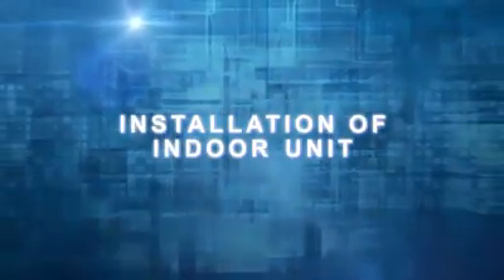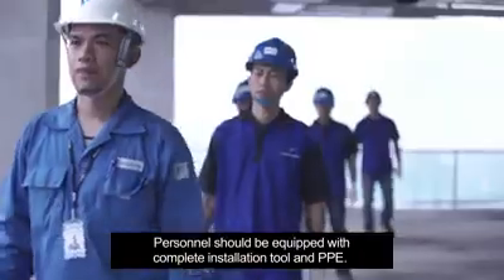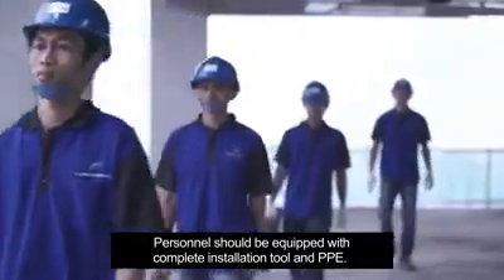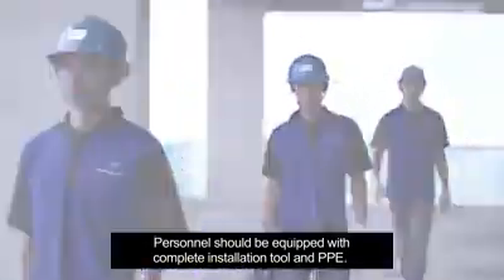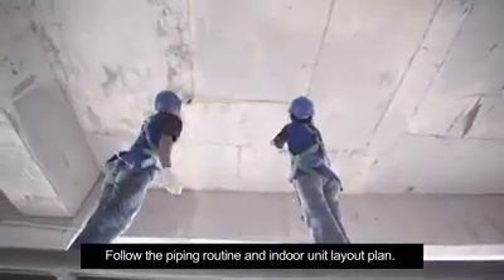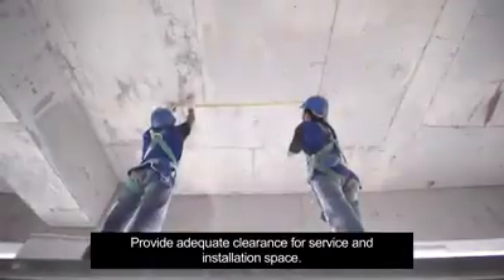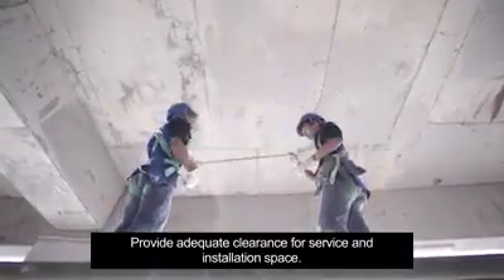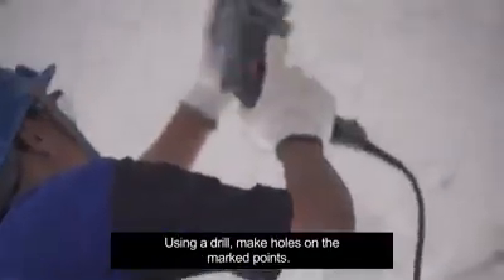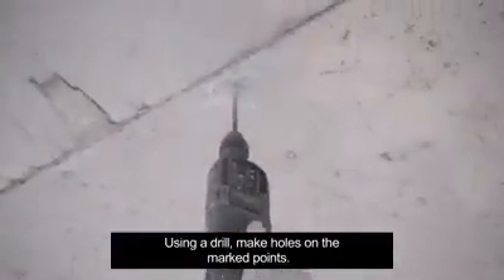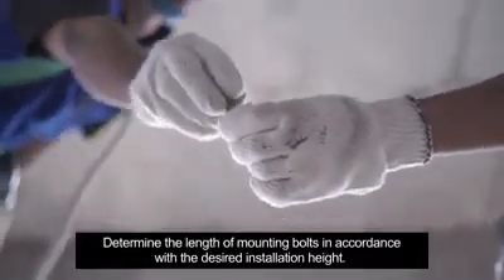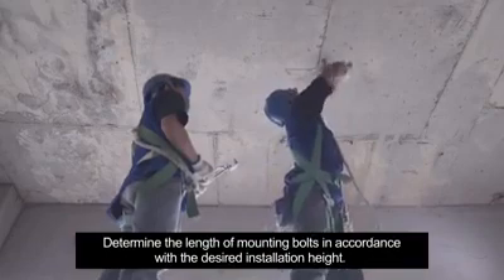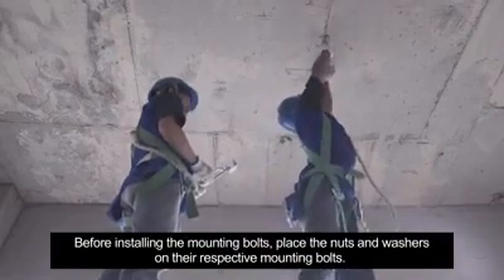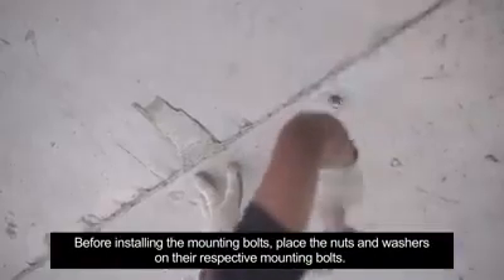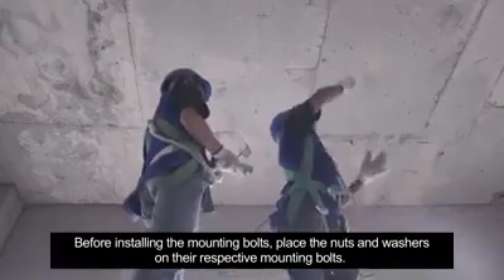Installation of indoor unit. Personnel should be equipped with complete installation tools and PPE. Follow the piping routine and indoor unit layout plan. Provide adequate clearance for service and installation space. Using a drill, make holes on the marked points. Determine the length of mounting bolts in accordance with the desired installation height. Before installing the mounting bolts, place the nuts and washers on their respective mounting bolts.